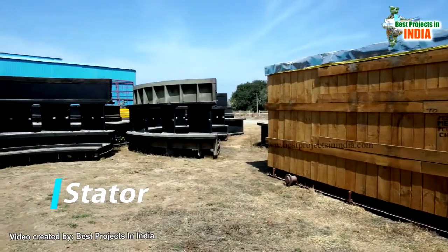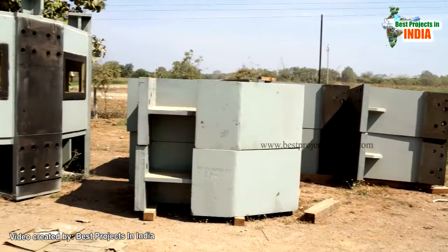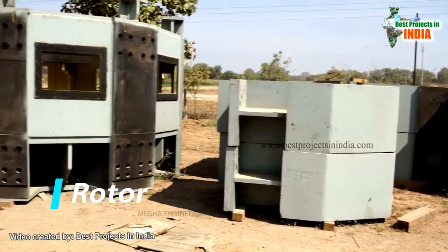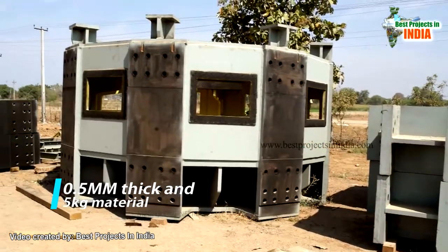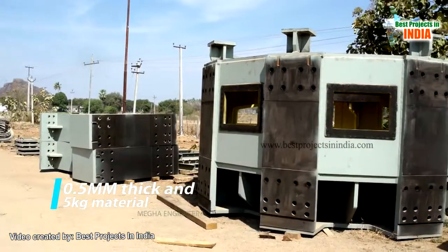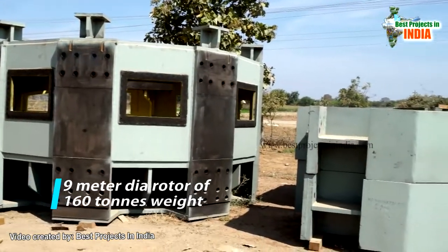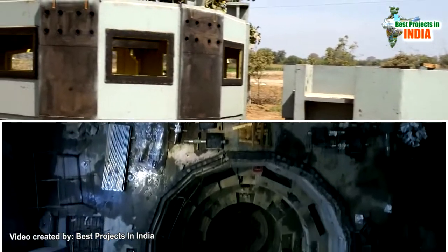The stator has a large housing with internal winding, received in four parts which are assembled and wound on site. The rotor is received in very loose items — 0.5mm thick, 5kg pieces. After build-up, it becomes a 9-meter diameter rotor weighing 160 tons. The rotor is inserted into the stator and coupled with the pump to run and deliver water.